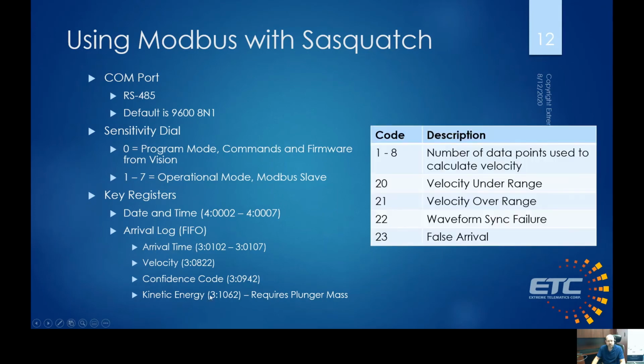For the confidence code, this is once again in the manual, but the different numbers obviously mean something different. Numbers 1 to 8 is telling us how many points we're correlating between the waveforms that are coming off of the magnetometers. So there's up to 8 data points that we can correlate. And then there's special codes that are in the 20s. So 20, 21, 22, 23 is velocity under range, over range. We're unable to synchronize the waveforms or capture the waveforms, or we start calculating and find out there's not actually an arrival.